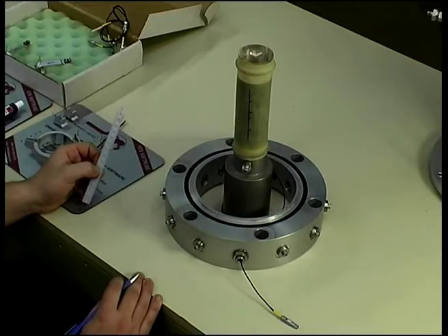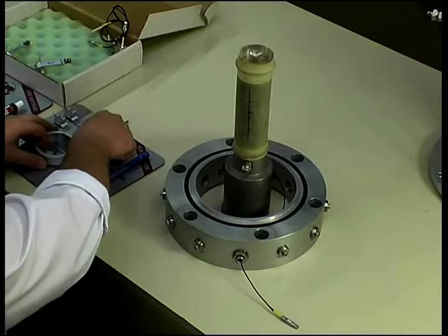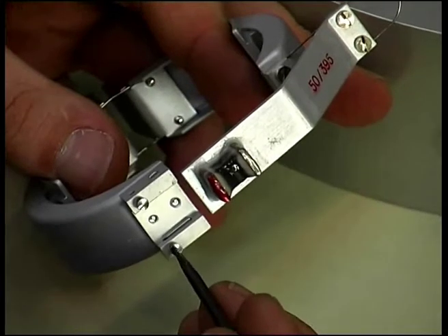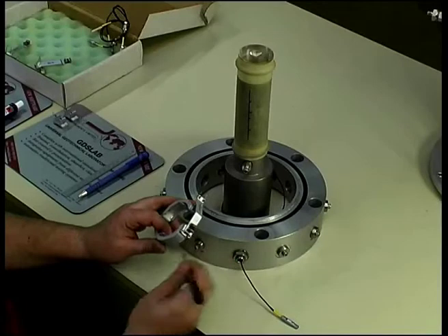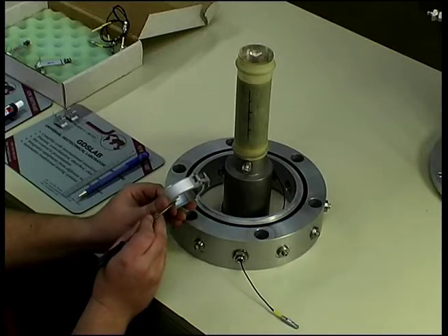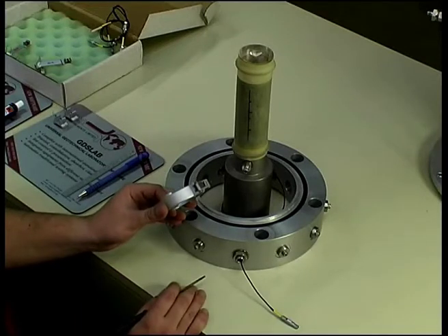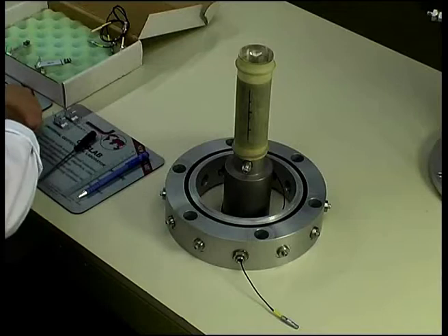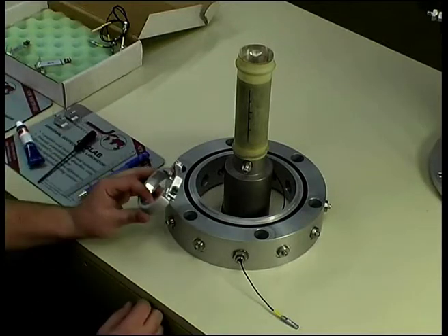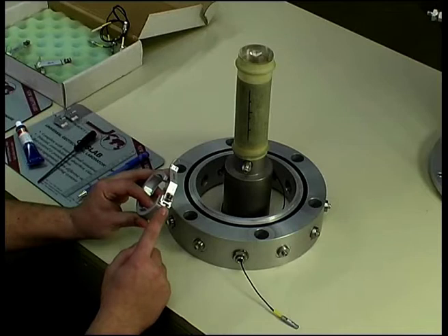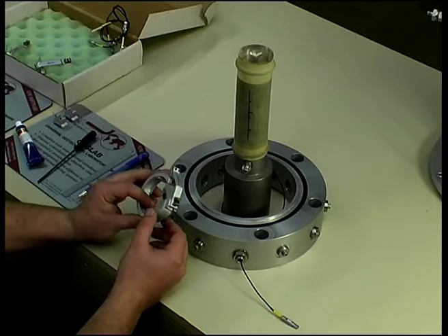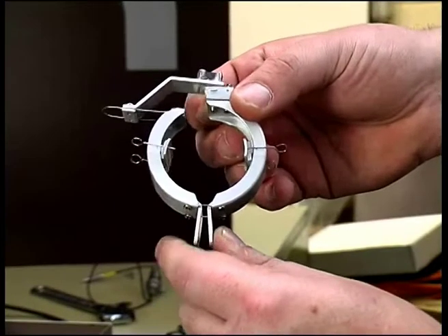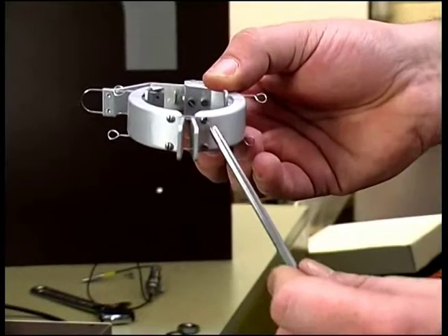Now on the radial caliper, we make sure all of the screws are loose, ready to accept the chip and pins are in place if we are using pins. We always place the radial caliper first as this goes inside the axial devices. We have the magnet arm in place on the radial caliper before mounting. We hold the radial caliper by the two hinge tabs. This holds the caliper at the maximum diameter. This open diameter may be increased by adjusting the screws next to the hinge.